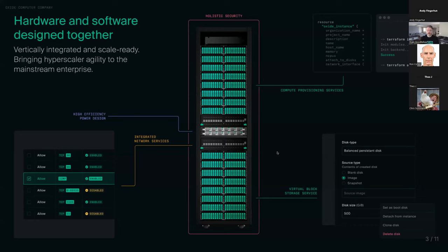We have two switches in the middle of the rack. They each have 32 QSFP28 ports hanging out the front. These are based on the Tofino-2 ASIC. Out the back, each switch connects at 100 gigabits per second over 100GBASE-KR4 backplane spec — to each compute sled. Each compute sled connects to each switch, so we have physical multipath for a high-availability network setup. In the very middle of the rack are a pair of rectifiers. We're DC throughout the entire rack, giving us power efficiency gains.